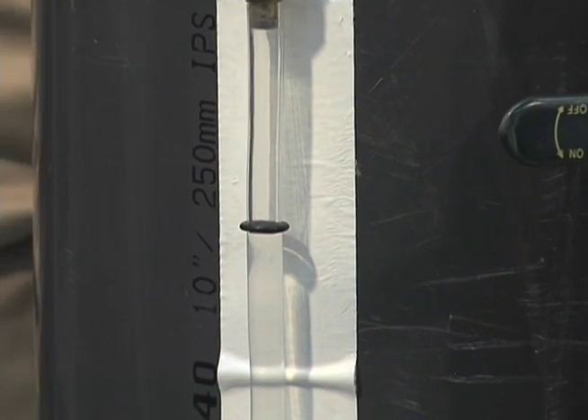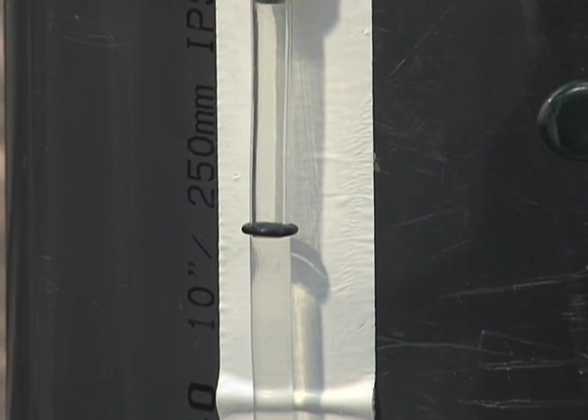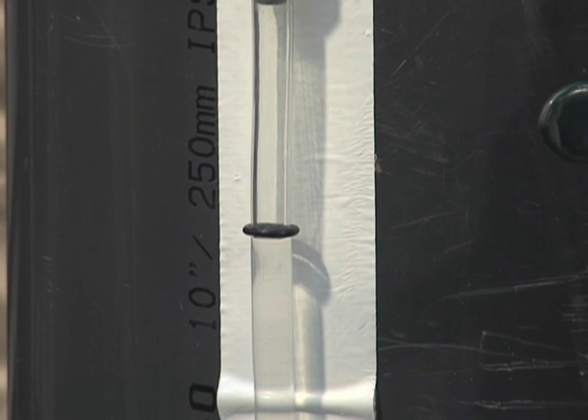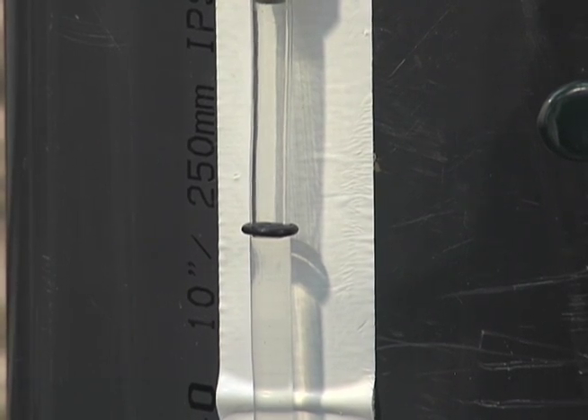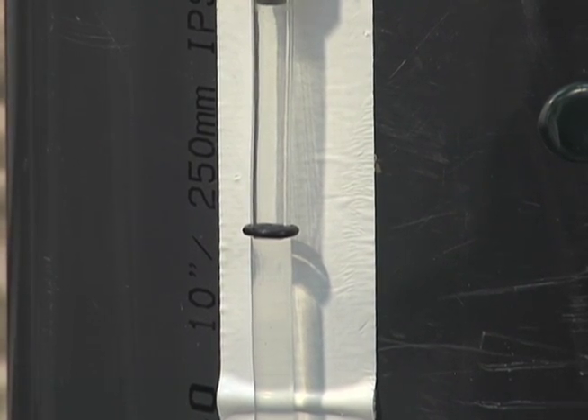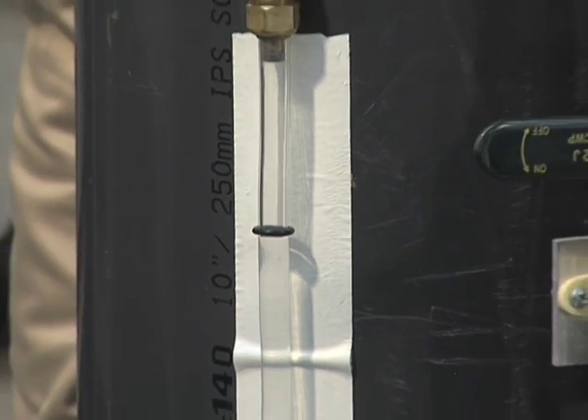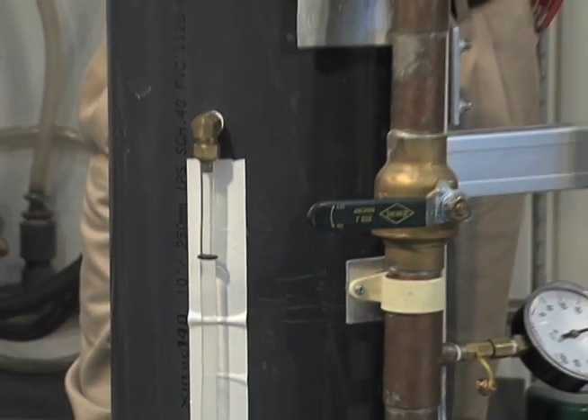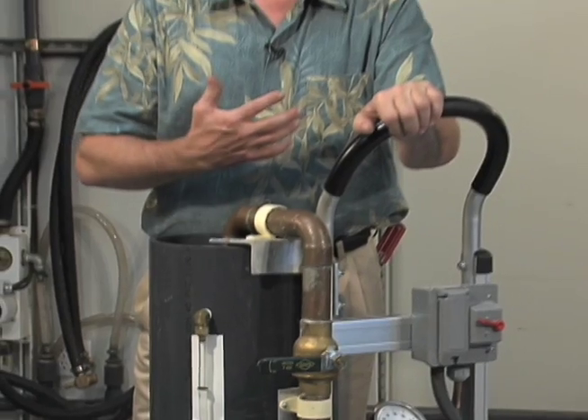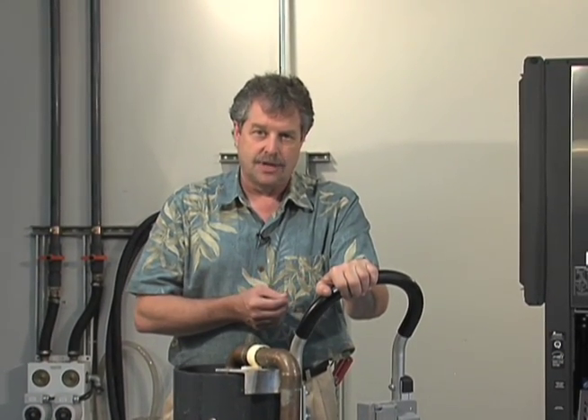And as you can see here, we have probably a 1/16 of an inch or so. So I'm very confident to tell you we don't have any air still in this system. So at this point, it's time to rotate our 3-way valves on our flow controller so that we're able to flush both the loop and the coaxial heat exchanger at the same time.